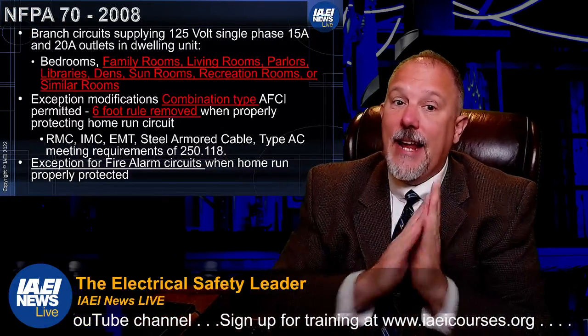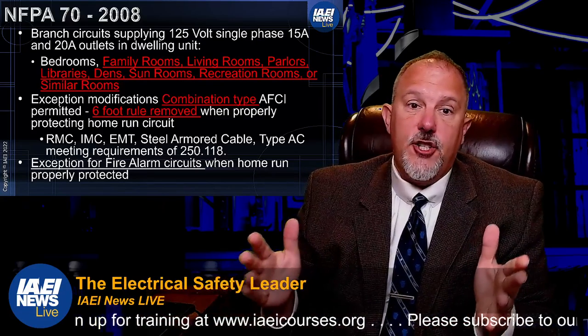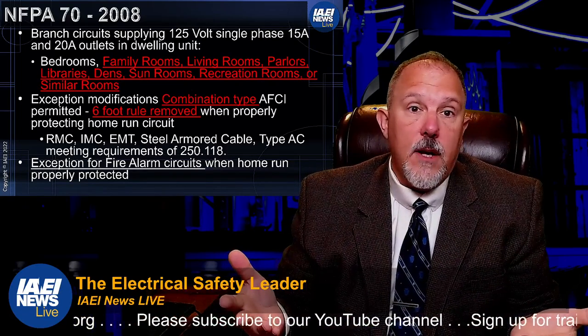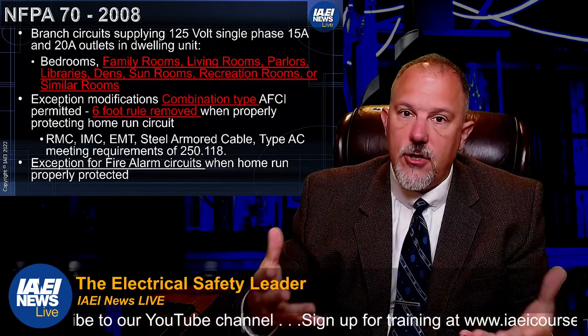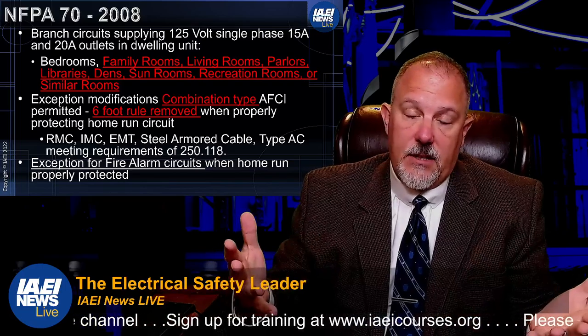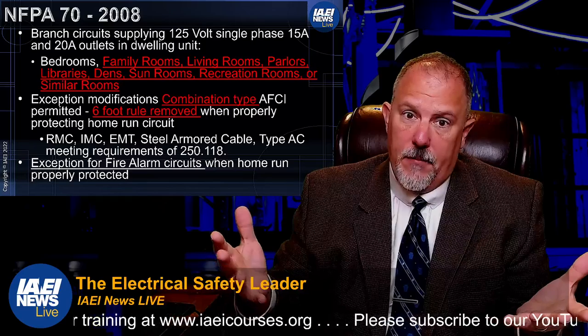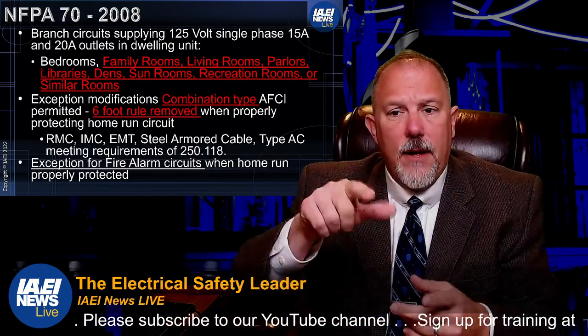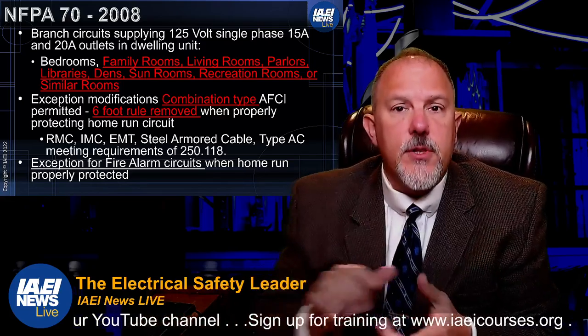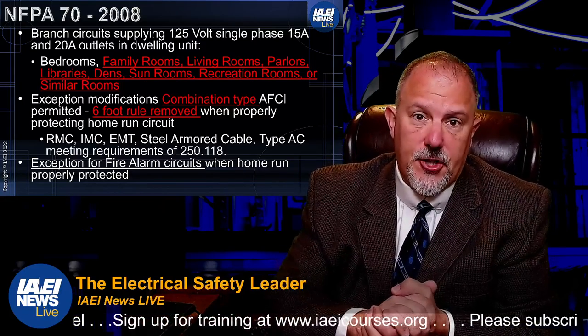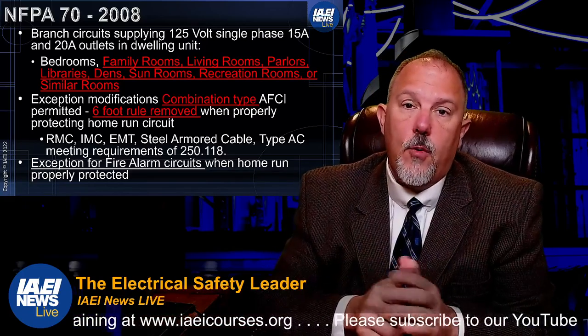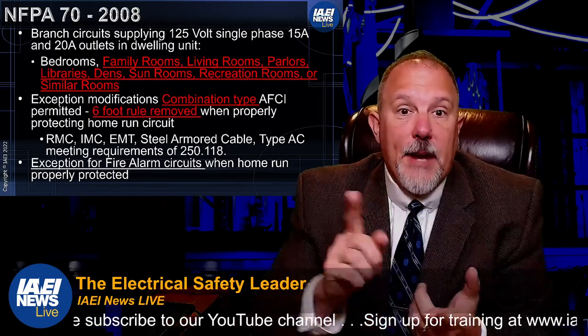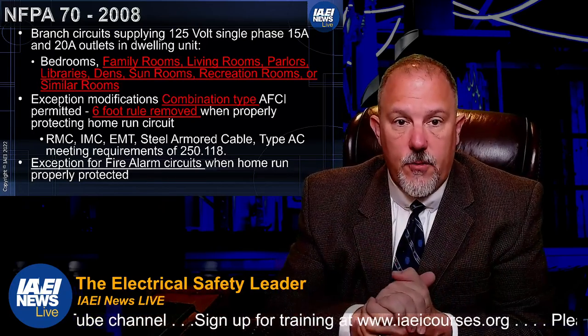In 2008, we saw expansion beyond just bedrooms, leveraging the same fire statistics. When a home is taken by an electrical fire, the problem doesn't choose one room over another — damaged conductors anywhere are the issue. NEMA's afcisafety.org has documented found problems due to arc fault circuit interrupters. We expanded to family rooms, living rooms, parlors, libraries, dens, sunrooms, rec rooms, and similar rooms.